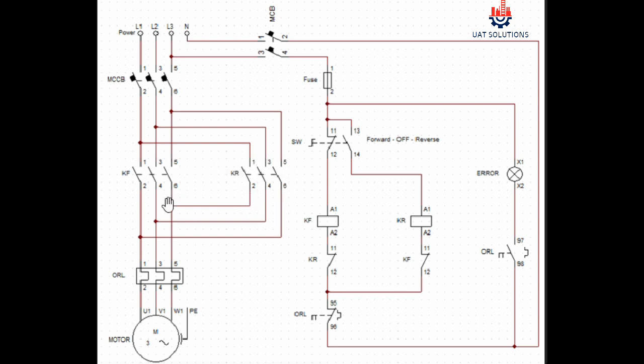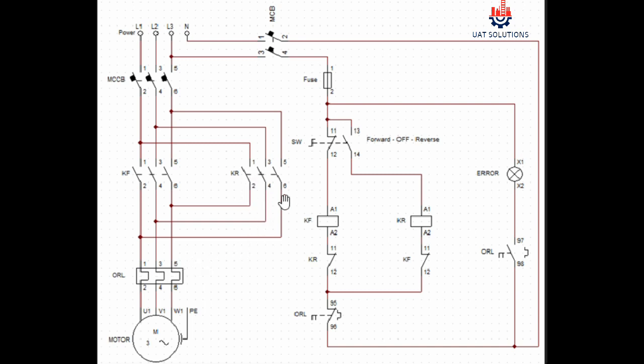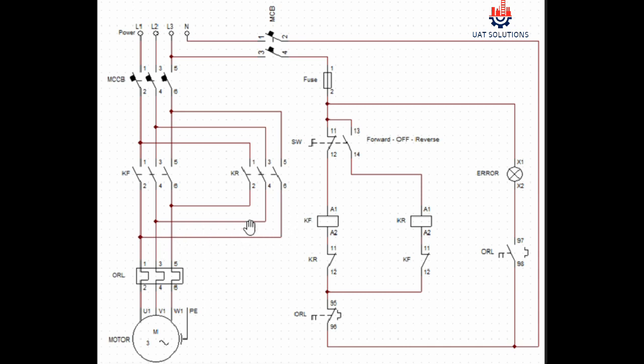The output terminals of contactor KF 2, 4, and 6 are connected to overload incoming terminals 1, 3, and 5. But the output terminals of contactor KR 2, 4, and 6 are connected to overload terminal 5, 3, and 1. If you notice we have interchanged L1 and L3 coming from contactor KR to the overload. This is done to run the three-phase motor in reverse direction.